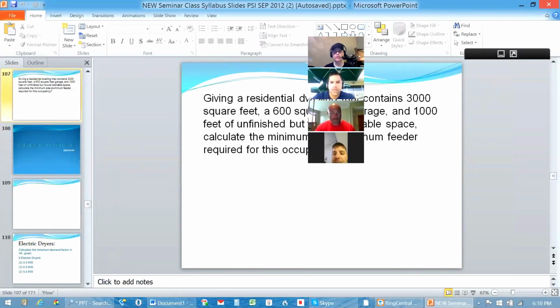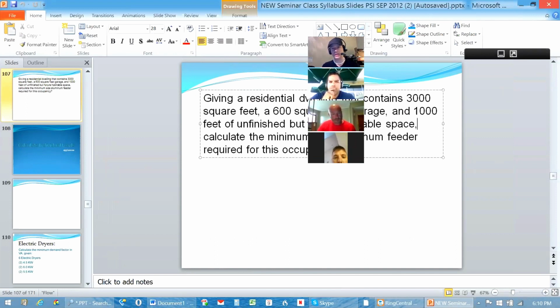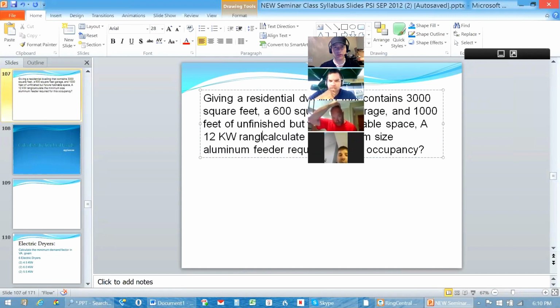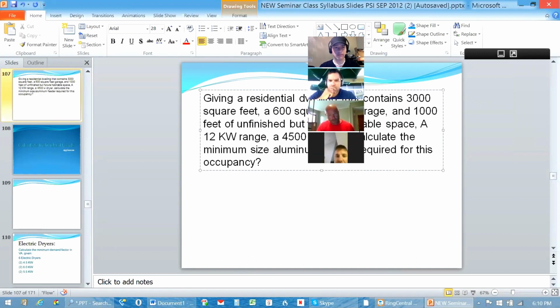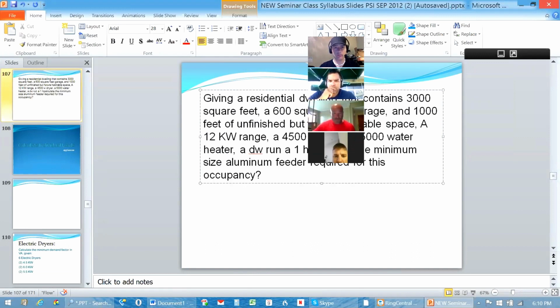Yeah. Okay. So if we had a residential dwelling with 3,000 square feet of livable space, a 600 square foot garage, and 1,000 square feet of unfinished but future habitable space, calculate the minimum size aluminum feeder required for this occupancy. I'm going to add some stuff in here because this is going to give us below the minimum standard. We won't get anywhere close to 100 amps on something like this. So let's do a 12 kW range, and we'll just do it as a single unit range, a 4,500 watt dryer, a 5,000 watt water heater, a dishwasher run by a 1 horsepower 120 volt single phase motor.